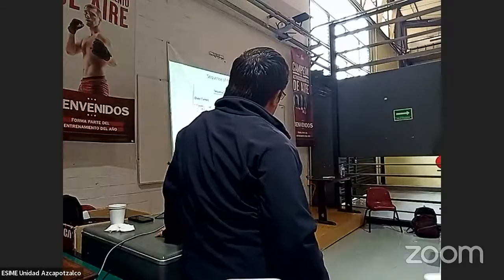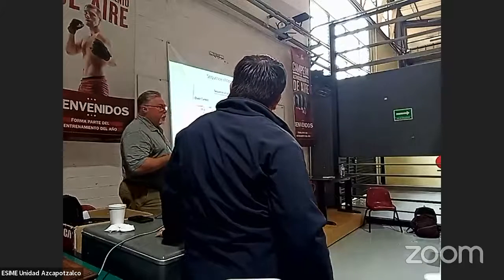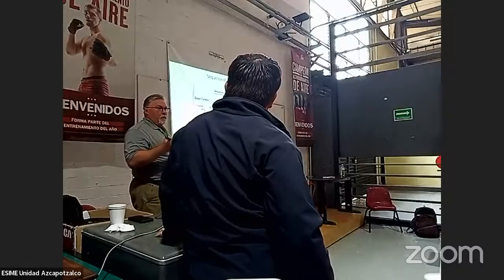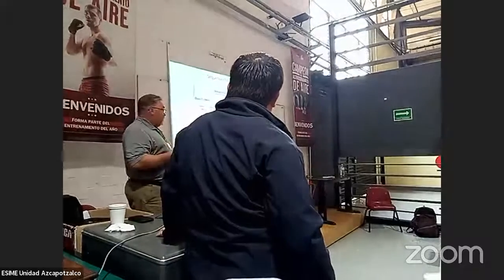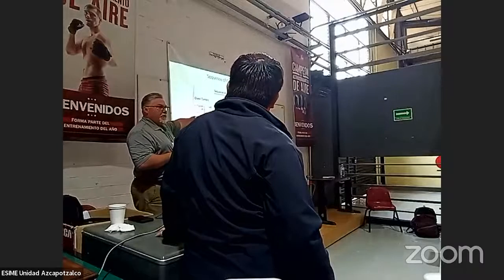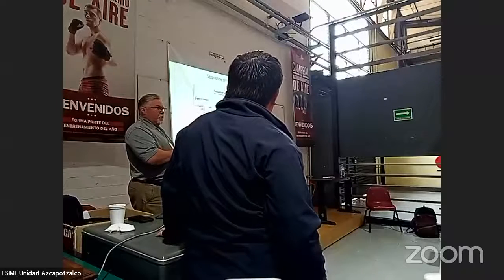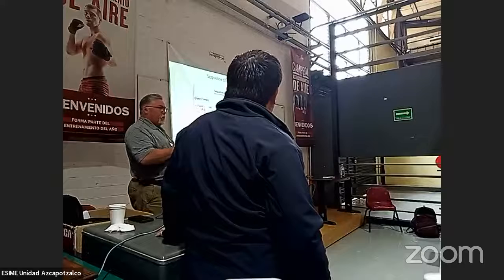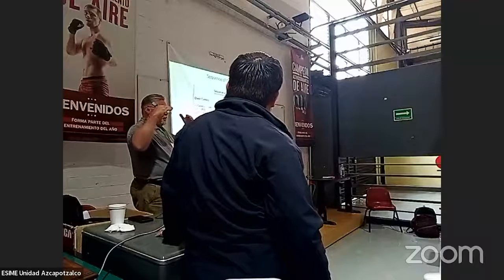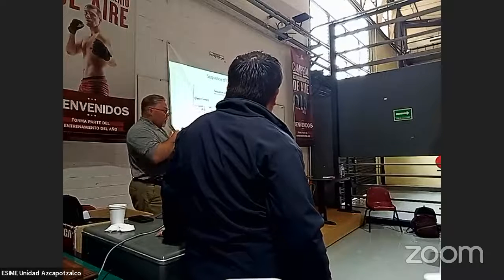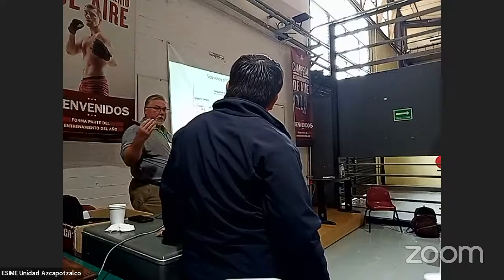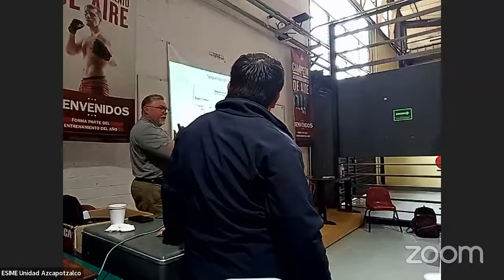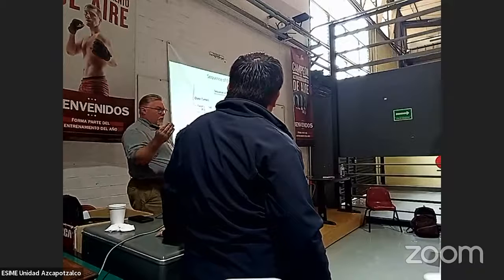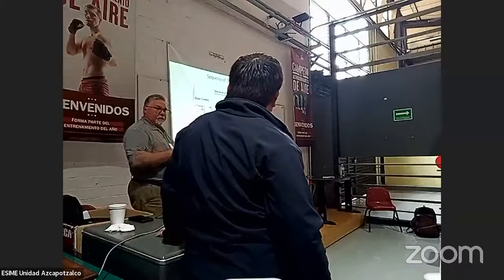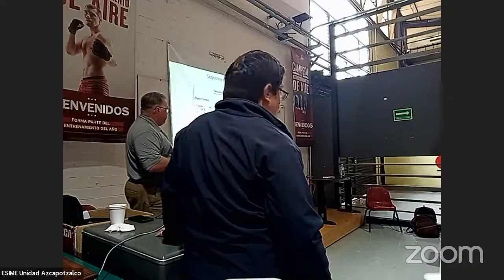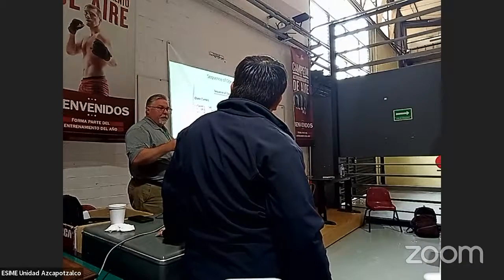So you should be somewhere between 2.5 and 3.0 compression ratio. Does that make sense? Low pressure plus 14.7, which is atmospheric pressure, absolute. High pressure plus 14.7. Divide high pressure by low pressure and that will give you the compression ratio. It should be around 2.5 to 3.0 roughly.